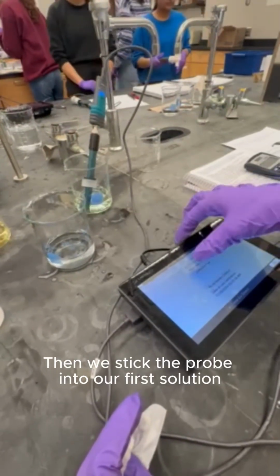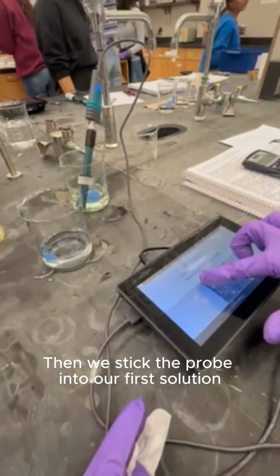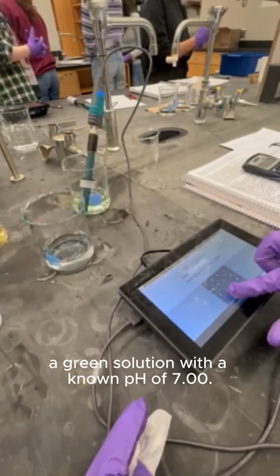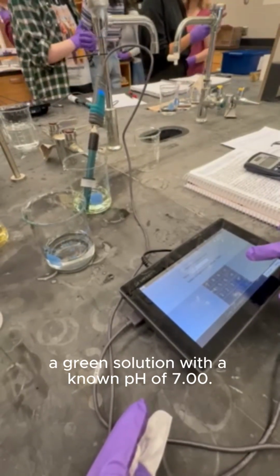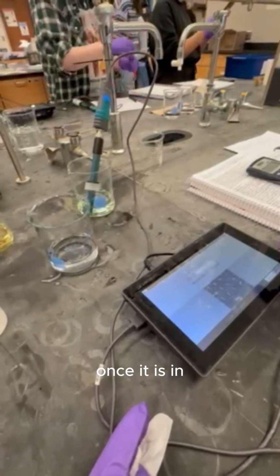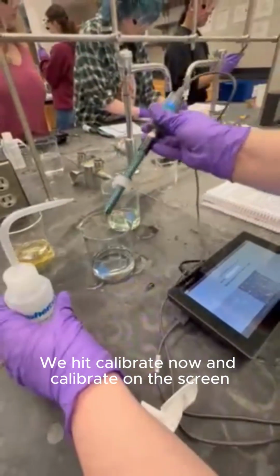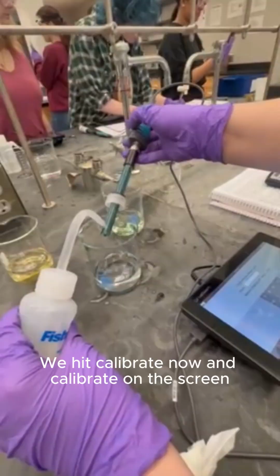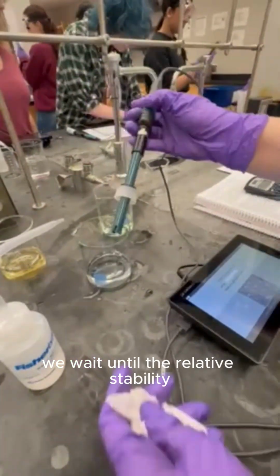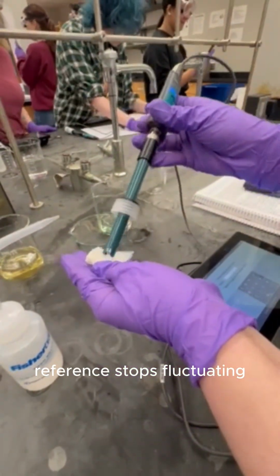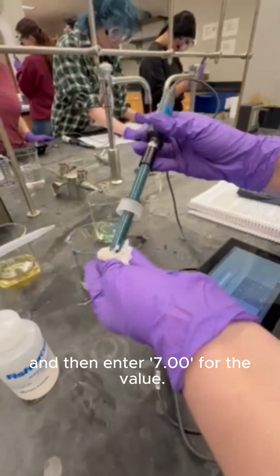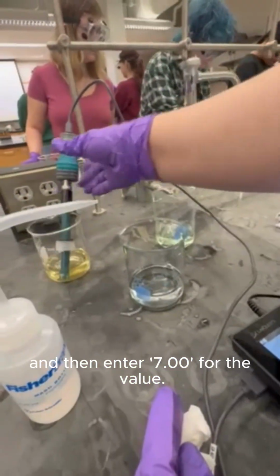Then we stick the probe into our first solution, a green solution with a known pH of 7.00. Once it is in, we hit calibrate now and calibrate. On the screen, we wait until the relative stability reference stops fluctuating, and then enter 7.00 for the value.